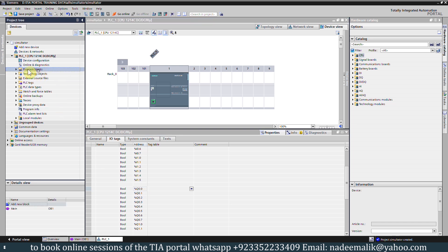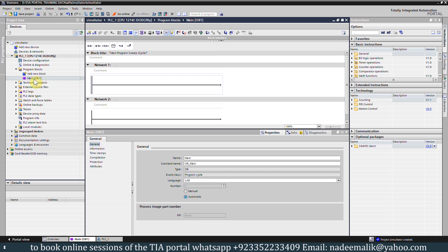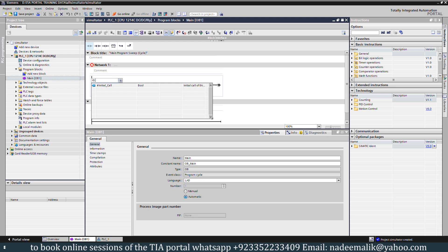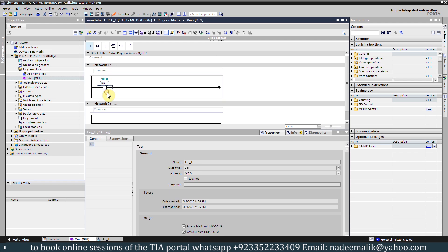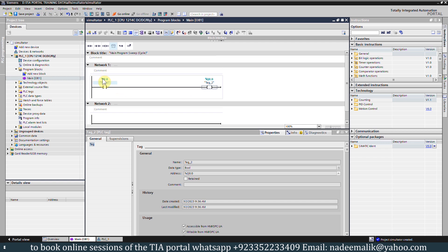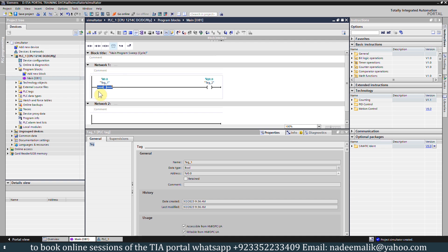Next we will go to the program blocks and double click on OB1. OB1 is the organization block number one and it is by default added into the PLC program. We will drag and drop a normally open contact and assign it the input address I0.0. Next we will insert a coil and assign it Q0.0. Whenever the I0.0 input is high, it will turn on the output Q0.0.